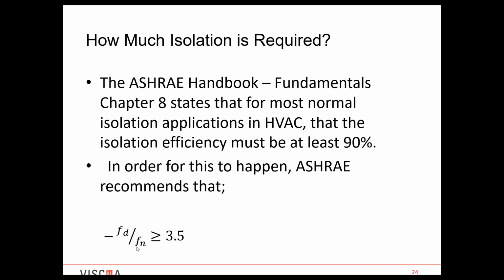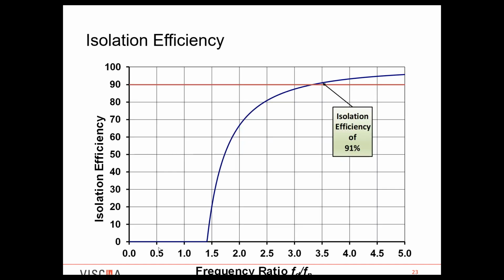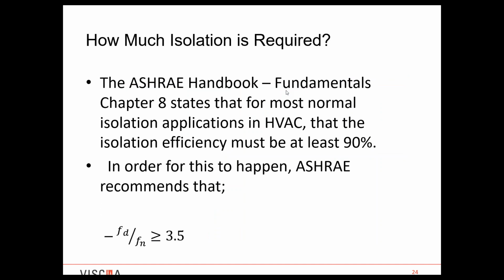So really, vibration can be very subjective. You'll have some customers who are very sensitive to the feelings of vibrations. You'll have some customers who are very sensitive to any sound that's created from the structure-borne noise of vibration. But again, if you get up at that 90% mark, you should meet the subjective goals of the people using that building. If you're a little bit less, if you're 85, 88%, you're going to meet most of those people. But again, the goal should be to try to get as close to that 90% isolation efficiency from the ASHRAE handbook as possible.